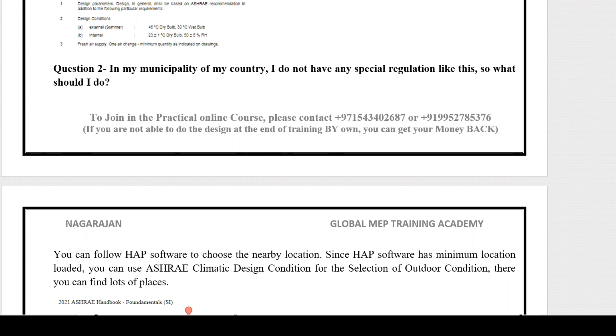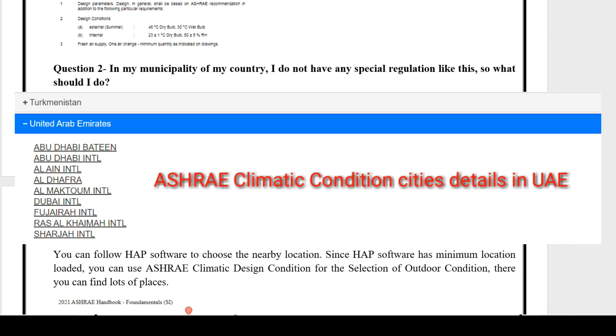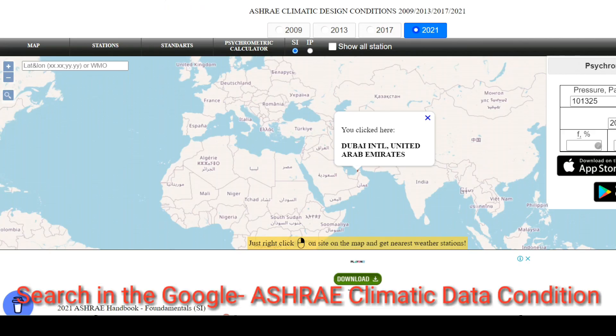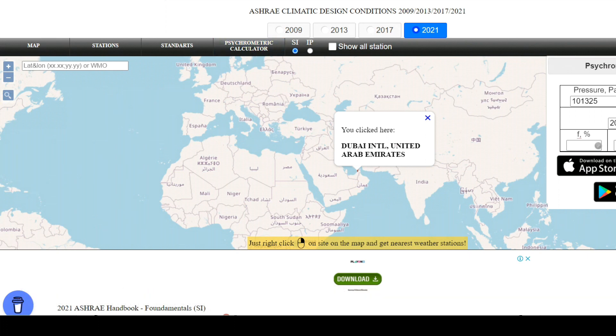If you're in a country without special regulations, you can follow HAP software to choose the nearest location, but HAP software has a limited number of locations. You can use the ASHRAE climatic conditions for selection of outdoor conditions — there you can find many more places. For example, in UAE, HAP only has Dubai and Abu Dhabi, but in ASHRAE climatic conditions there are many more locations like Sharjah. In GCC countries like UAE or Qatar, we have special regulations for temperature, so we follow those rather than ASHRAE climatic conditions.